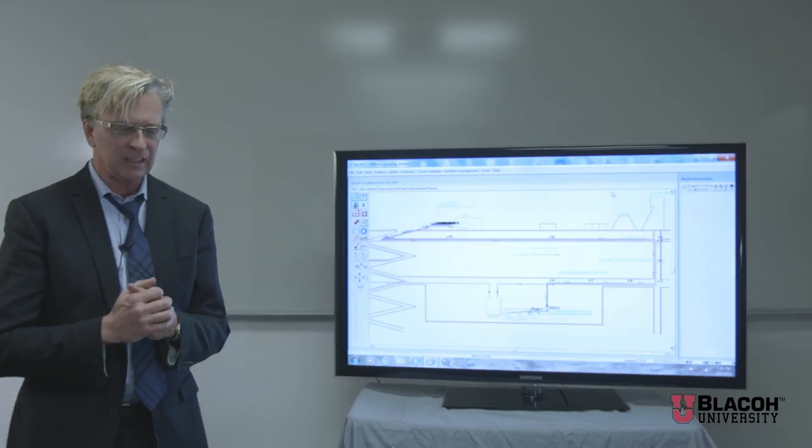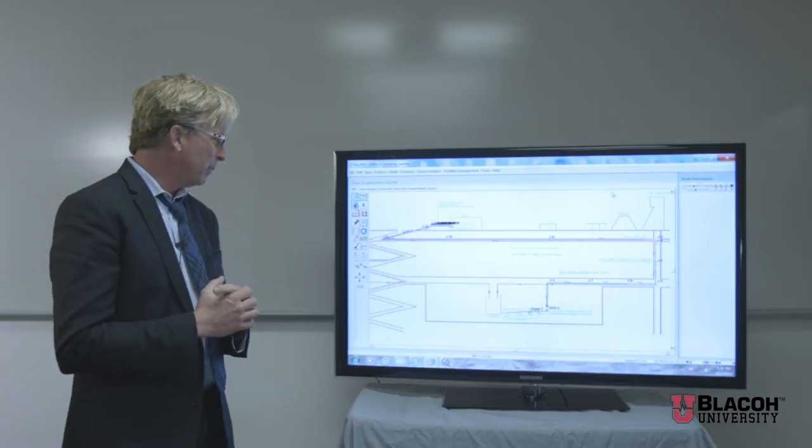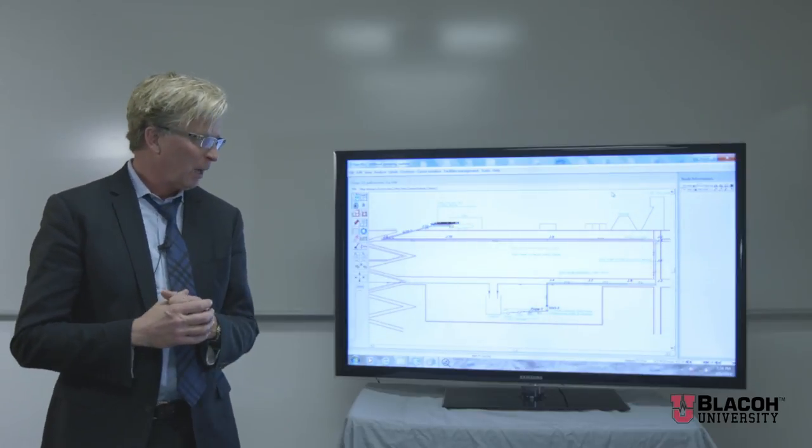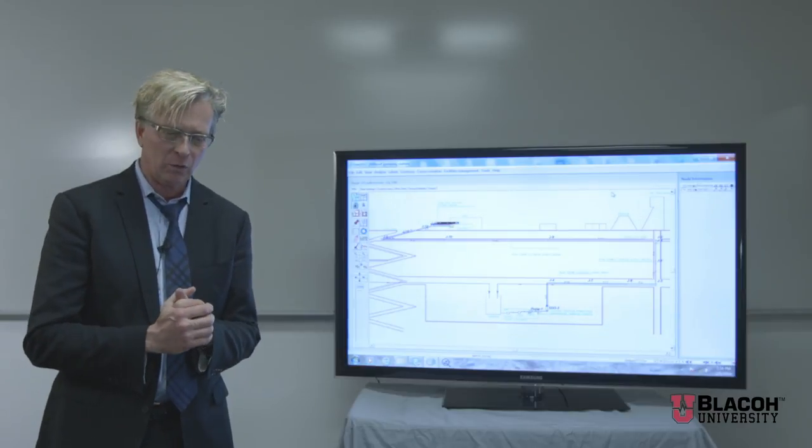Again, the better way of depicting that wave oscillating back and forth in your piping system. You look at this chain of events, and we're going to look at some surge analysis in a minute and what happens when we have a pump trip or valve closure. When we have a pump trip, if we go into cavitation, what is cavitation? It's when our fluid is going from a liquid to a gas and then coming back into a liquid. We're going to look at an example of that shock wave based on a KY Pipe surge analysis of a gold mine in Canada.